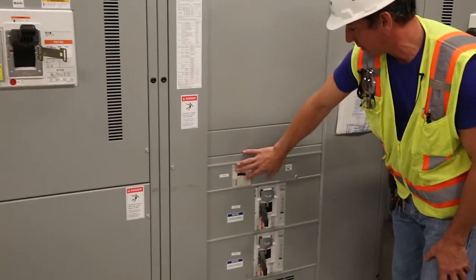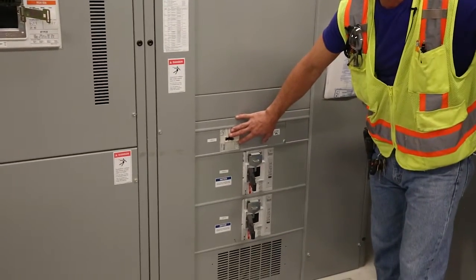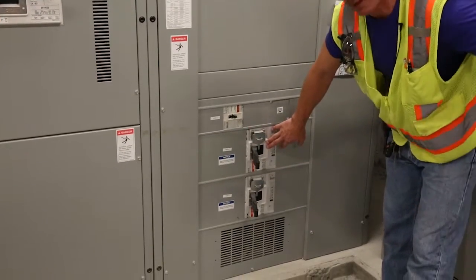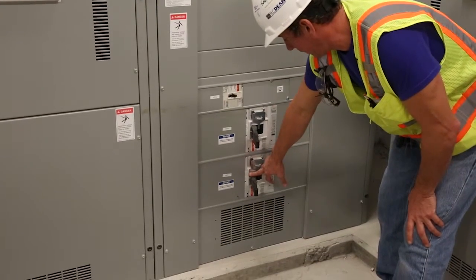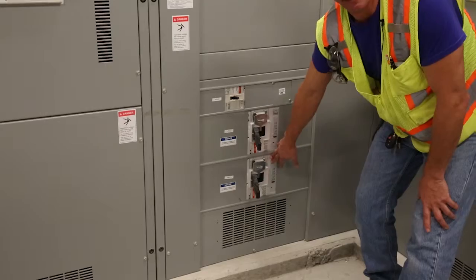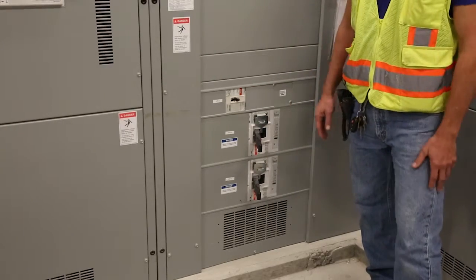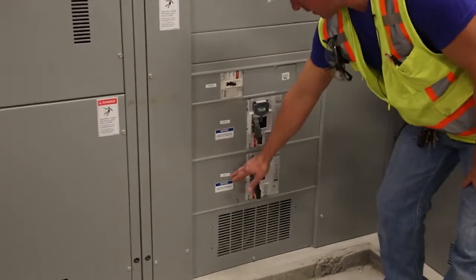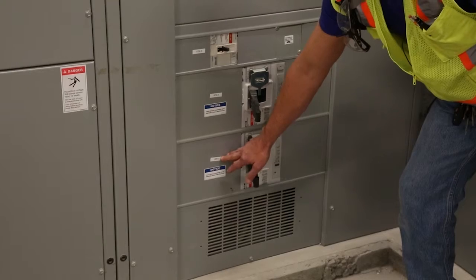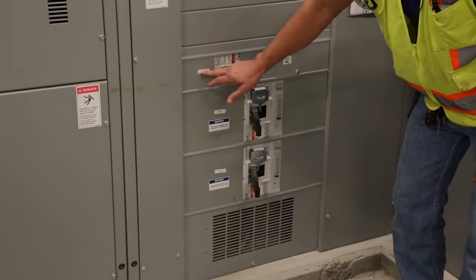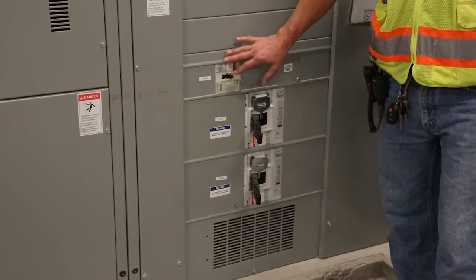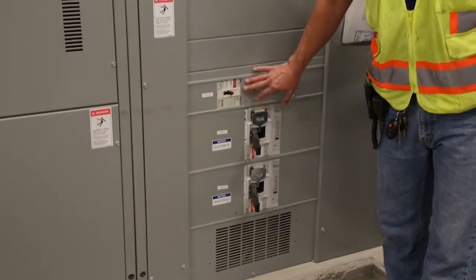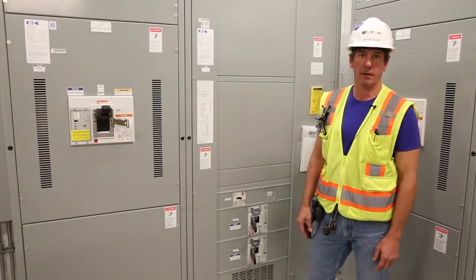ATS3, you'll have the cables coming off of ATS3 going directly to the ATS. Then you'll have ATS2, same as well, going right to ATS2. The cables from HDP don't go to the ATS, they bypass that and go straight to the distribution panel. So in an emergency situation, HDP will be dead. But when ATS2 and ATS3 drop out, the generator will kick on, power will transfer over, and it'll distribute the power out to those areas.